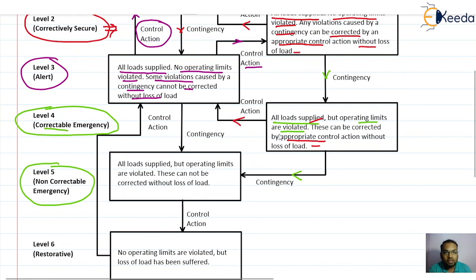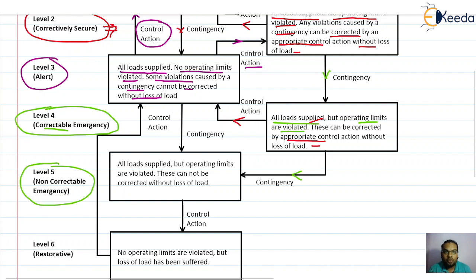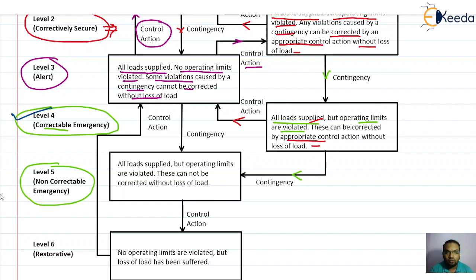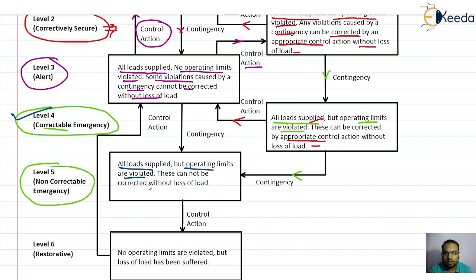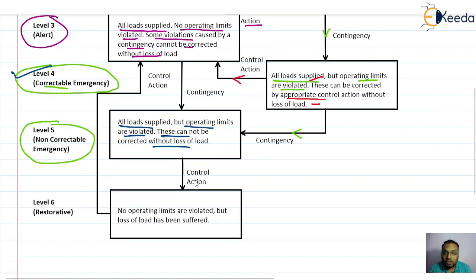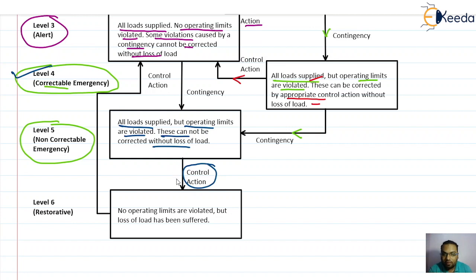If no control action is taken in level four, we will enter level five — the non-correctable emergency. We cannot correct that emergency directly. Up to level four, with some control action we were able to go to level three, and from level three it was possible to go to level one or two. But when we enter level five, we cannot directly go back from level five to upper levels — level four, three, or two. In level five, loads are supplied in the beginning but operating limits are violated with more severe violations, and these violations cannot be corrected without loss of load. To correct those violations, we need to cut off some load.